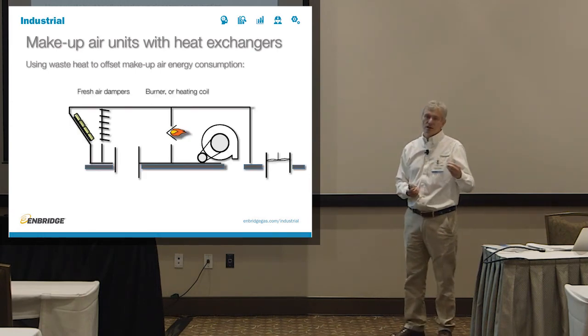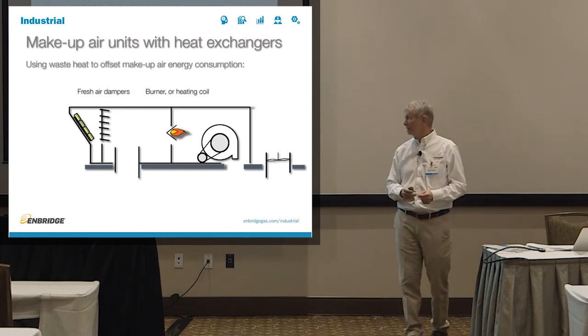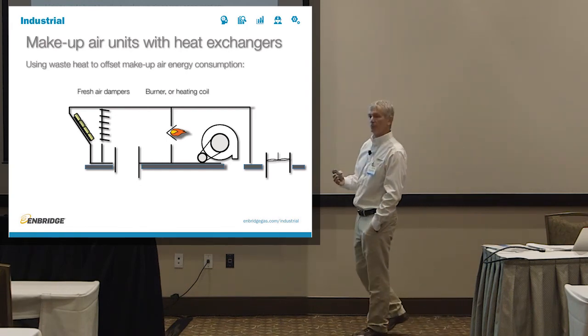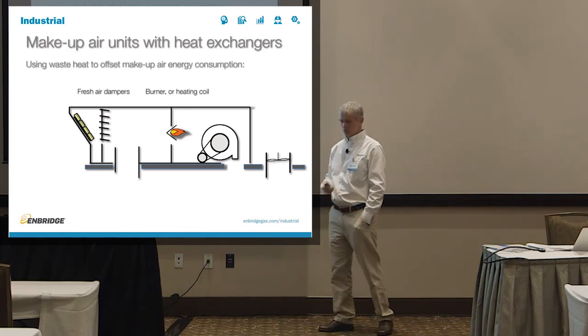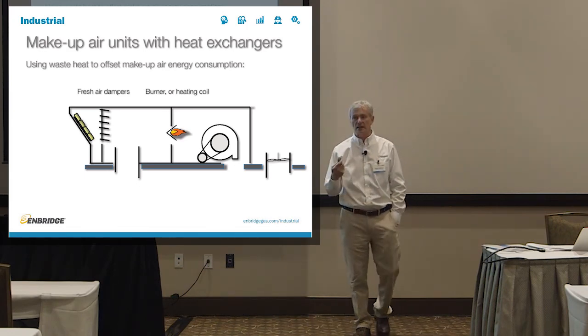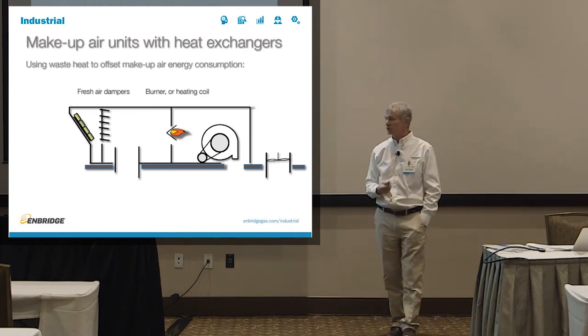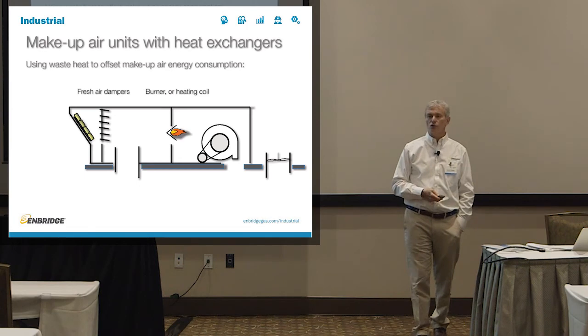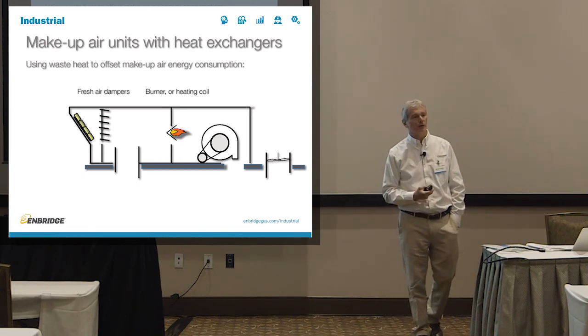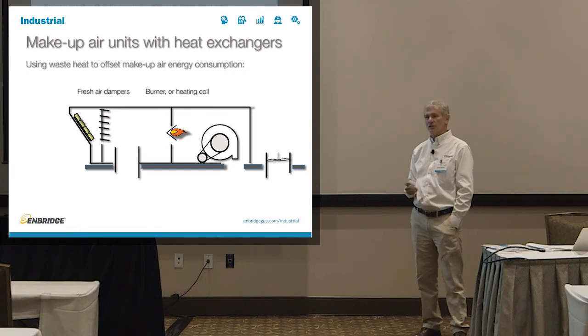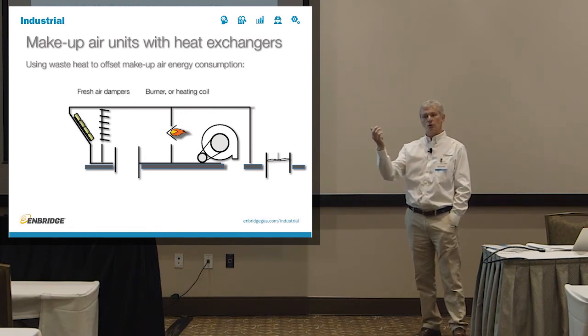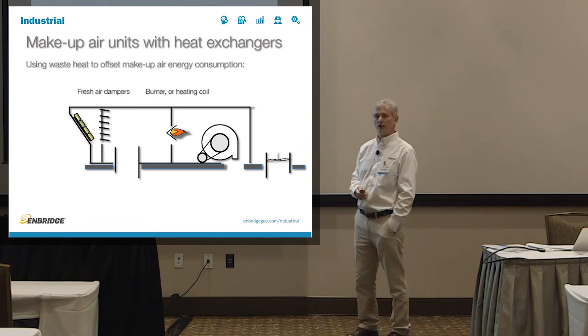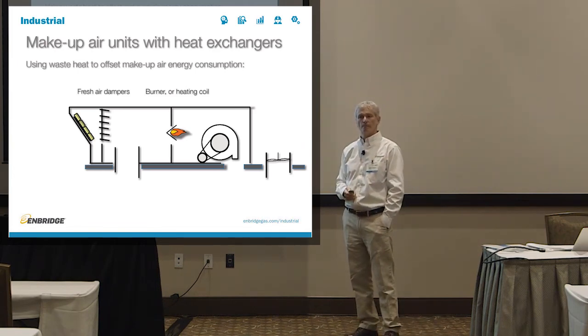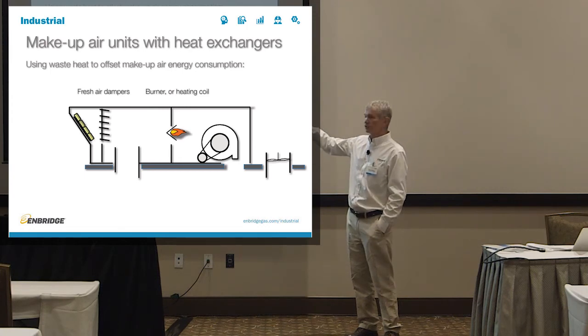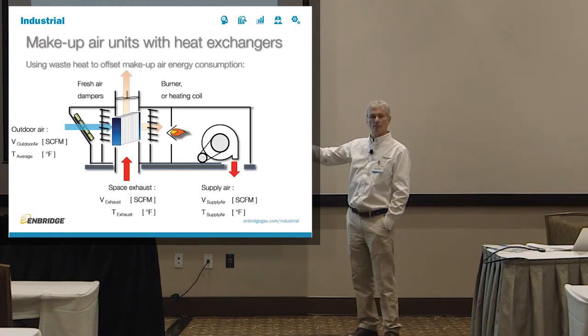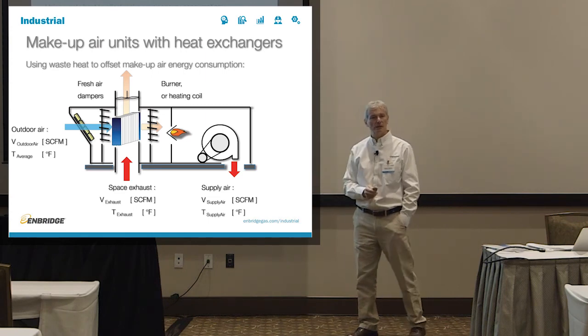So what happens if you have makeup air and now you want to use some of that waste heat? You can purchase makeup air units these days that will take the space exhaust and put it essentially inside the unit and force that exhaust to go over the heat exchanger that's placed before the burner in the makeup air unit. So the space exhaust leaves the space, goes through the air-to-air heat exchanger, and preheats the outdoor air before it gets to the burner. And now you have essentially reduced the amount of energy you need in your burner by the waste heat recovered in the heat exchanger prior to it.